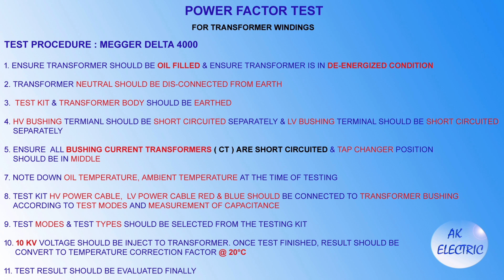Ensure the transformer is oil filled and in a de-energized condition. The transformer neutral should be disconnected from earth. The test kit and transformer body should be earthed. HV bushing terminals should be short-circuited separately and LV bushing terminals should be short-circuited separately. Ensure all bushing current transformers are short-circuited and the tap changer position should be in the middle. Note down oil temperature and ambient temperature at the time of testing.